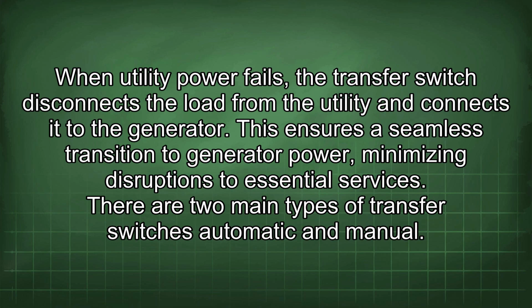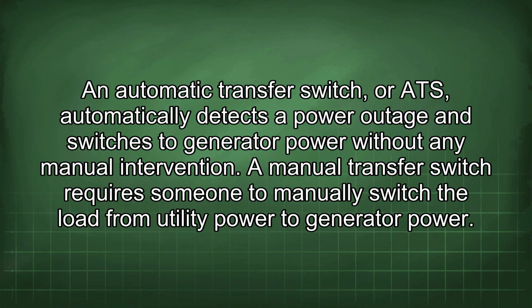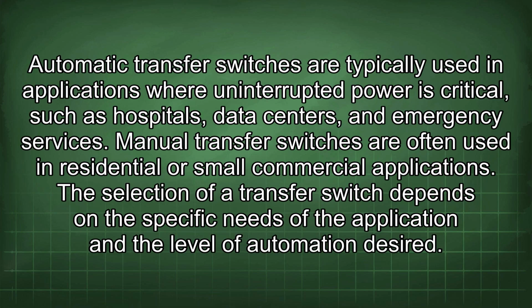There are two main types of transfer switches: automatic and manual. An automatic transfer switch, or ATS, automatically detects a power outage and switches to generator power without any manual intervention. A manual transfer switch requires someone to manually switch the load from utility power to generator power. Automatic transfer switches are typically used in applications where uninterrupted power is critical, such as hospitals, data centers, and emergency services. Manual transfer switches are often used in residential or small commercial applications. The selection of a transfer switch depends on the specific needs of the application and the level of automation desired.